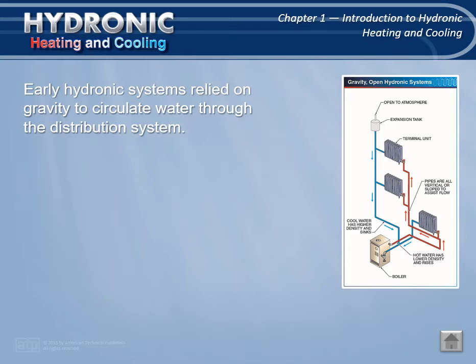Gravity flow systems commonly employed low temperature of boiler water. Because of this, terminal units and connecting pipes must be sized relatively large to meet the calculated heat loss of the building. The response to changes in outside weather conditions is slow.